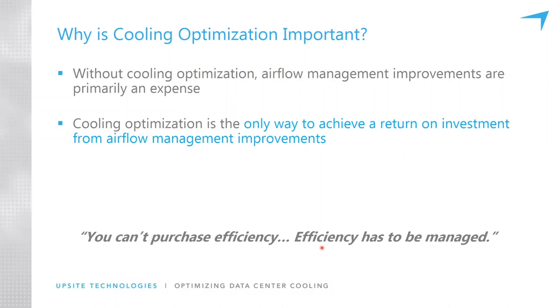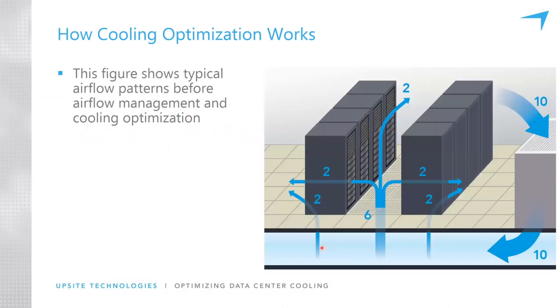So I've beat up on that enough. Let's talk a little bit more about how this balancing works. This starts with a very important consideration, which is bypass airflow. We're going to look at a number of slides here that show the airflow volumes through the room. This is a simplified example of a room that has one cooling unit and two rows of IT cabinets.